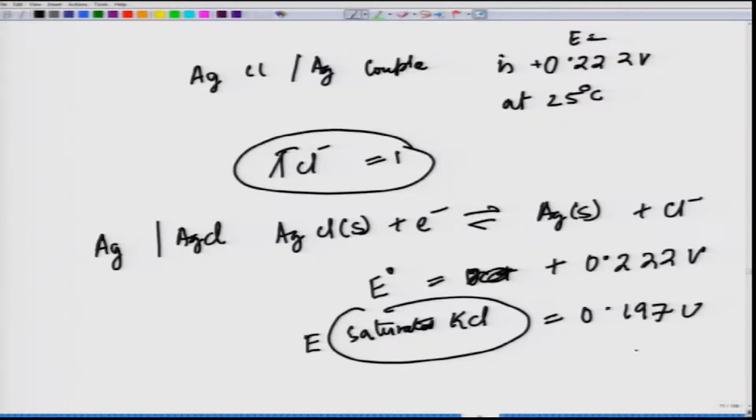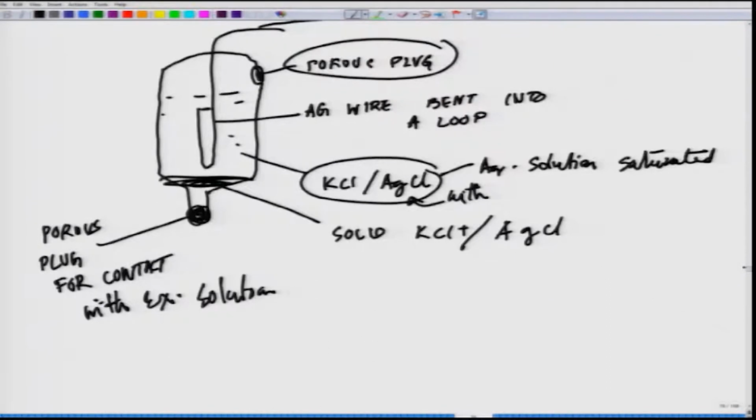The problem with reference electrode is that the porous plug becomes clogged. Okay. So, these are some of the practical problems you will come across. This plug is getting clogged. There are clogging problems, thus causing sluggish unstable electrical response. Some designs incorporate free flowing capillaries in place of porous plug. Other designs allow you to force fresh solution from electrode through the electrode analyte junction prior to the measurements.